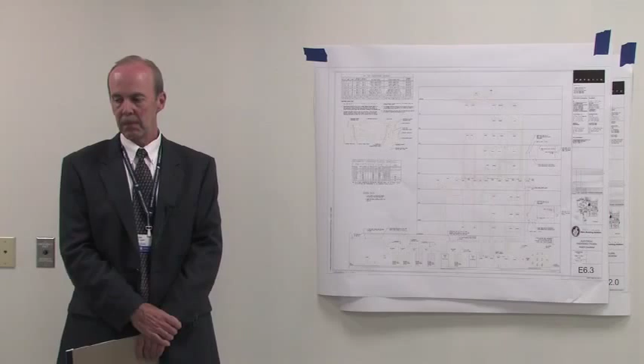If 3 engines can handle everything, you're just gonna keep on going, that's it. But if you have a problem with loading, then they'll start to shed off. Well, if you remember, during the design stages, we proved that out. We took the loads and we itemized them. We came up with the lighting and the power.